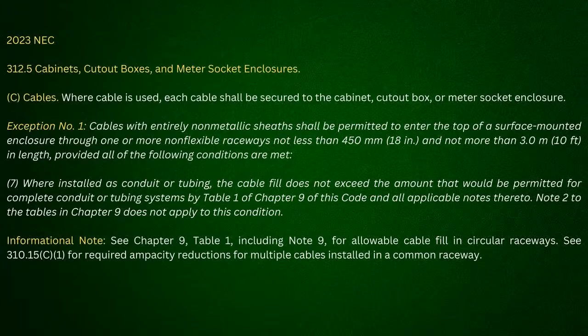Hold on a second. There's an informational note as you look at Note 9, and we'll get into that in a little while, where it talks about the required ampacity reductions for multiple cables installed in a common raceway. But what I want to point out is that a common raceway means a raceway system, something metallic from end to end, which I'm going to show, and you have to be connected in there. Then there are some reductions that have to apply. So this informational note has nothing to do with what they're requiring in 7. They're saying this is another informational note about cable fill in circular raceways. But they go through and tell you about reductions for multiple cables installed in a common raceway. That's what I'm going to get into and show you where they're applying this wrong, because they're not looking at other parts of the NEC.